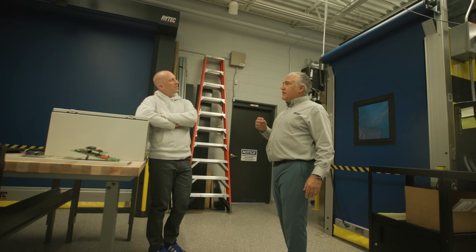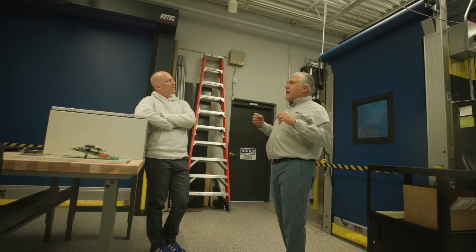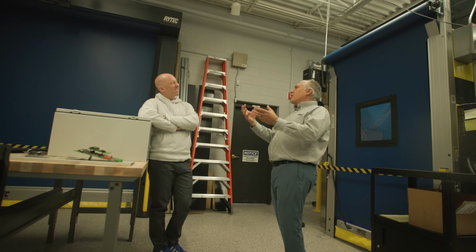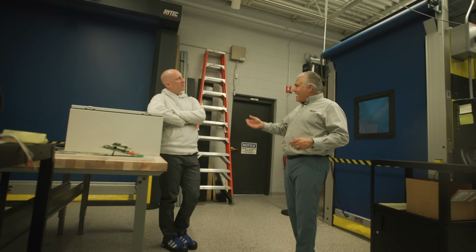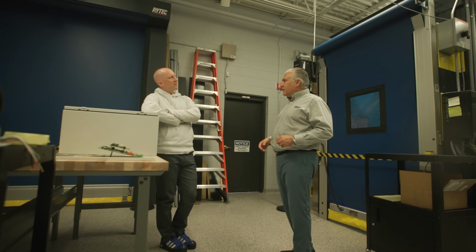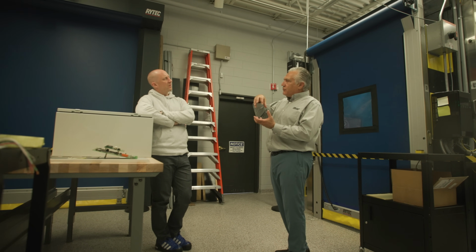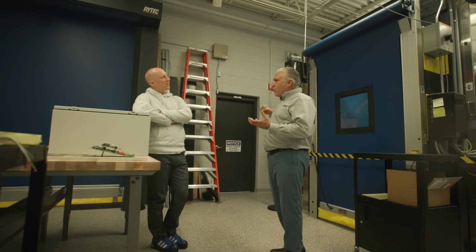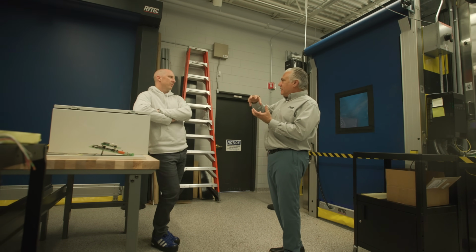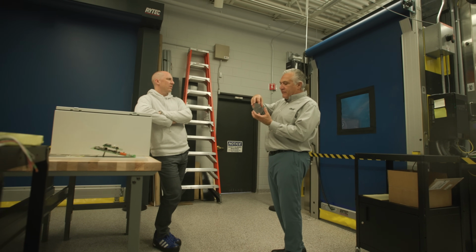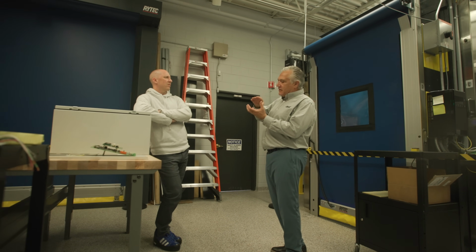If it's three phase, the only thing we ask you to do is set a jumper configuration that ensures all three of the motor drive capacitors get the same amount of current, because in high cycle applications, that's where the weakness comes in. The drive system relies on capacitors to store the energy required for the inrush. Think of them as tanks of electrical current. Every time they're not able to be replenished quickly, they just get weaker and weaker.